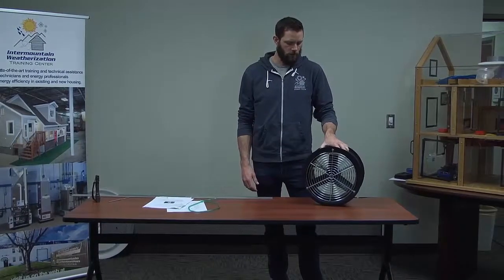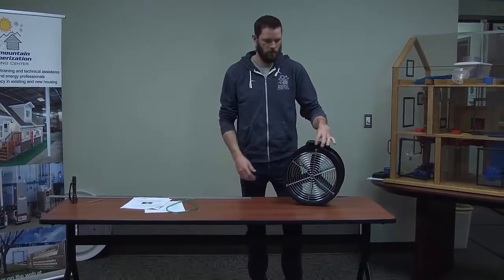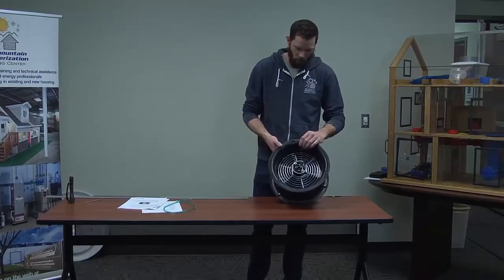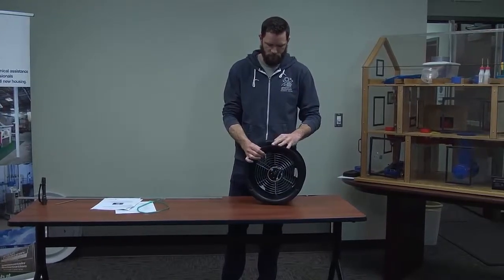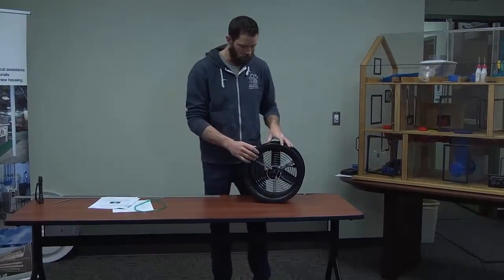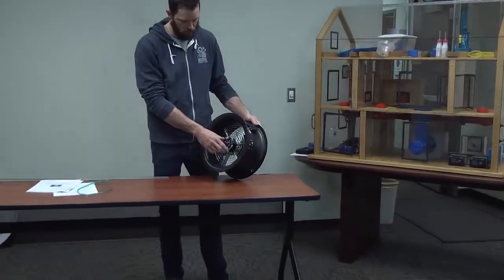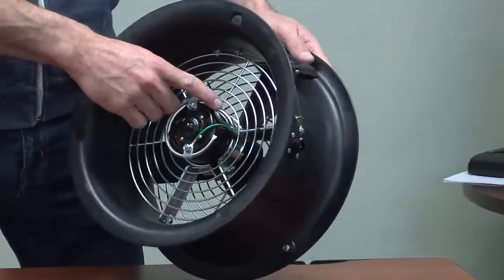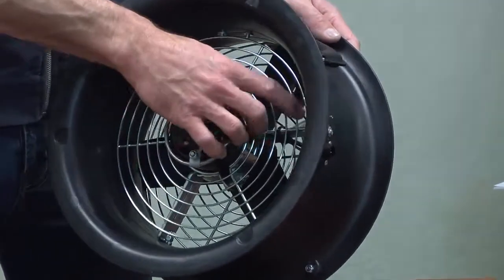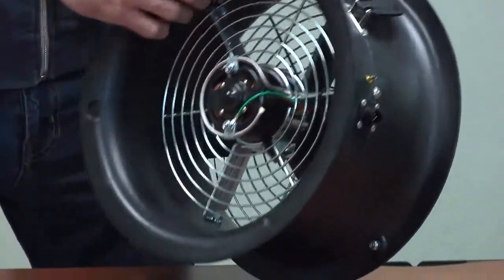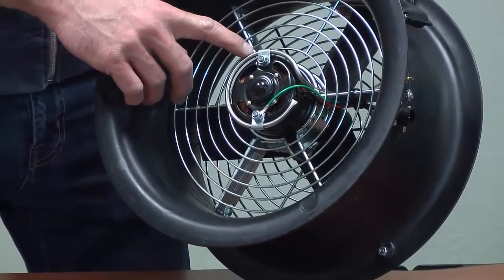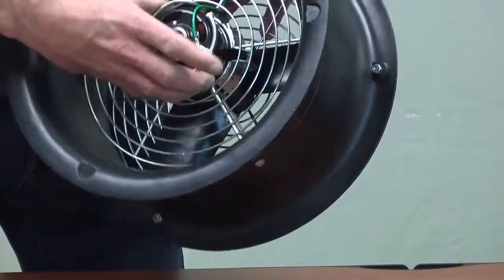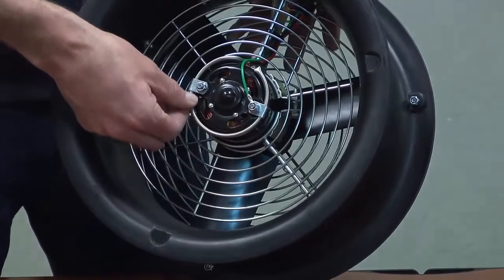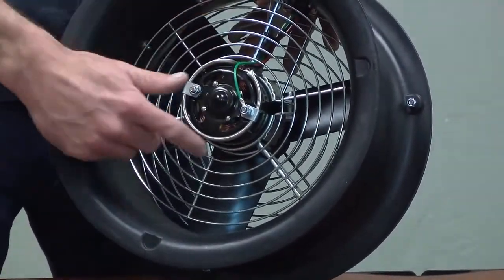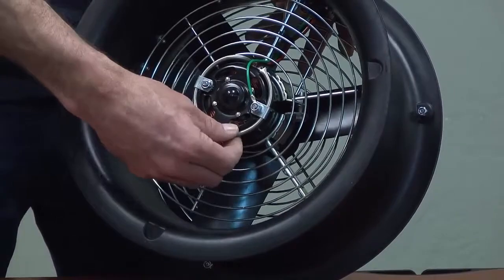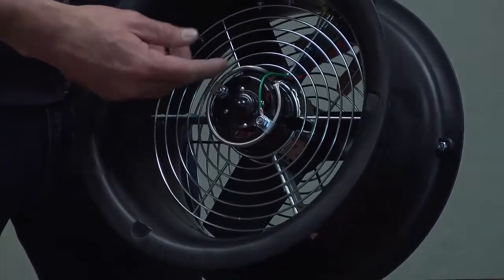So we're gonna do the field check on the Duct Blaster B model. And we're kind of doing the same checks as we did on the blower door. We're gonna do a visual check of the flow sensor and the housing and the tubing running from the flow sensor to the port. And we start off with our visual inspection. You're just making sure that this steel tubing, which makes up the flow sensor, is not bent and doesn't have any holes in it.